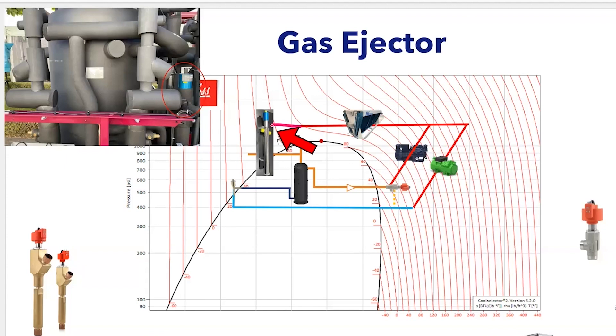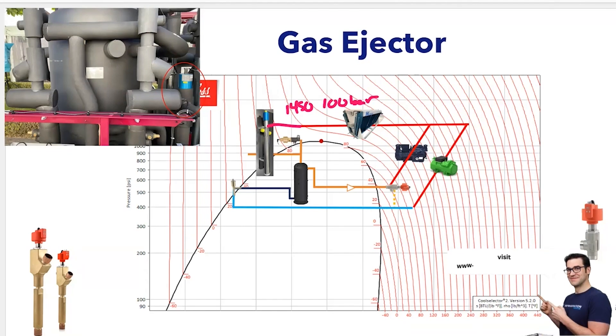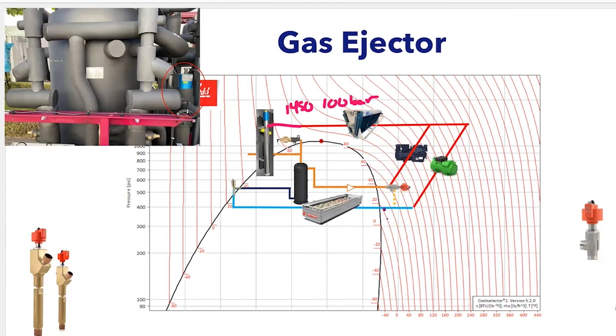This would come into the ejector. You get this high pressure gas coming in here, say 1450 PSI, 100 bar. That's coming down our drop leg. From our medium temp, we're going to take the suction gas and do a loop around here. Now all this suction gas leaving those medium temp evaporators will go into this ejector.